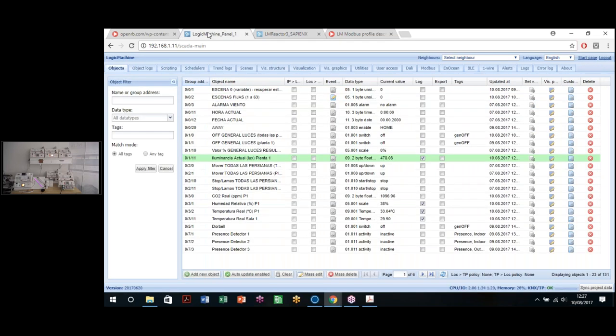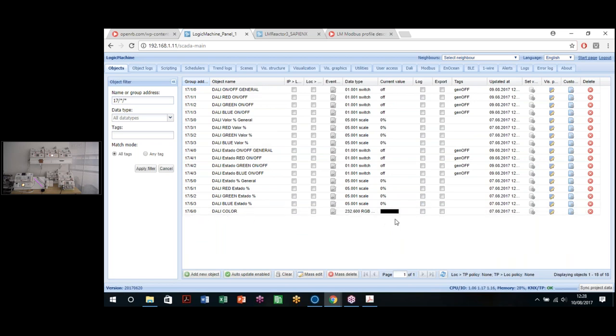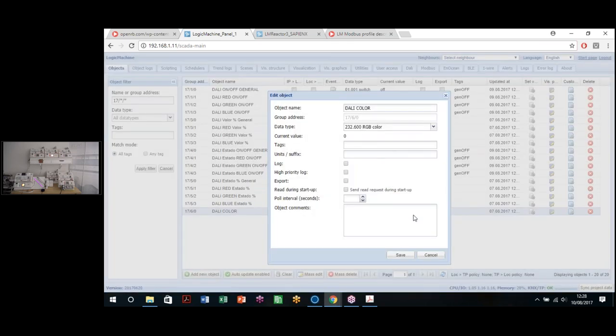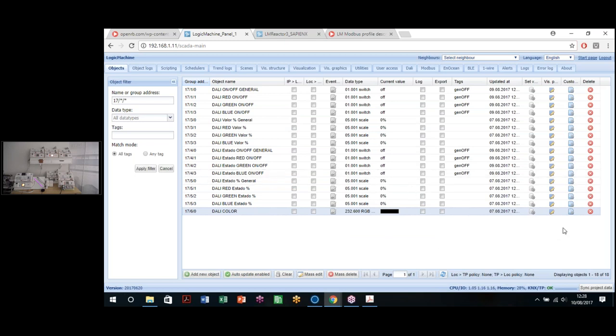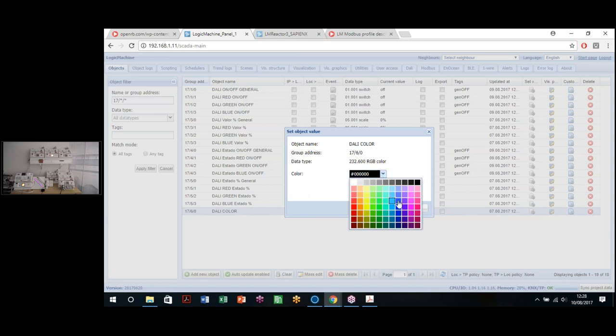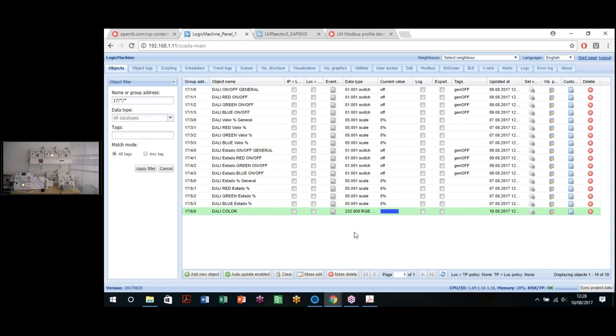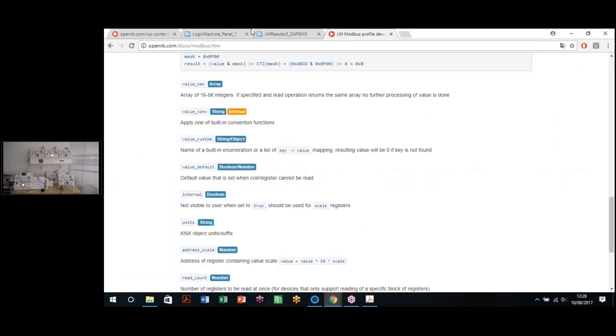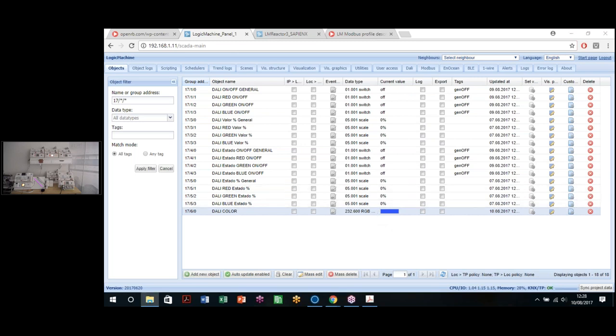So for that, I'm going to use a small script using the address 17.30. Let me see for a second. Okay, I'm going to use the DALI color. I've created an object called DALI color that we're going to set to a data type of RGB color. So this object, when we click on set value, will show us a color palette that we can select the color that we need. We click, and when we click save, the script that I'm going to create will send the specific color for the specific channel of the ballast. This example, we can find it also in the example section of the web page, and also we have it on the material that I've sent you. For that, we go to script, and we go to the...